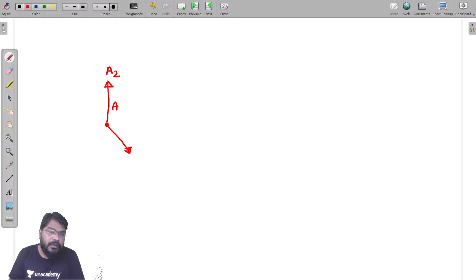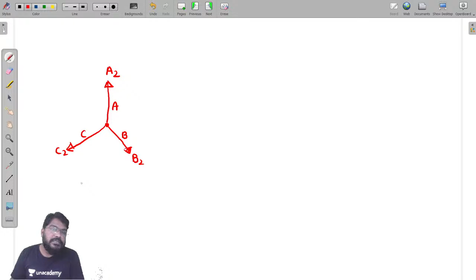Next, after this, the B phase winding. The outgoing terminal is B2, so it is the B phase winding. And after that, the C phase winding, whose outgoing terminal is C2. Now verify the phase sequence here. The phase sequence is equal to ABC. Now, in a similar manner, we have to draw the secondary delta connection.